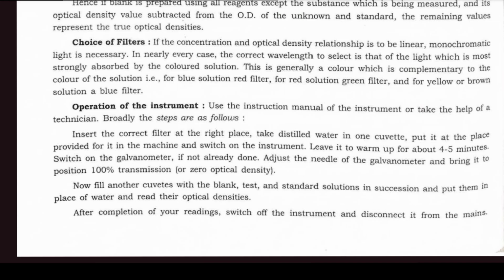Choice of filters. If the concentration and optical density relationship is to be linear, monochromatic light is necessary. In nearly every case, the correct wavelength to select is that of the light which is most strongly absorbed by the colored solution. This is generally a color which is complementary to the color of the solution, that is, for blue solution a red filter, red solution a green filter, and for yellow or brown solution a blue filter.